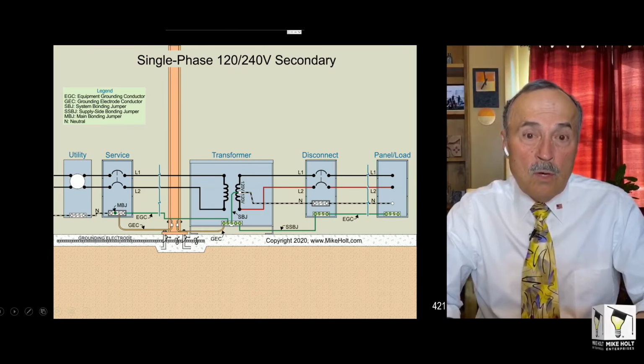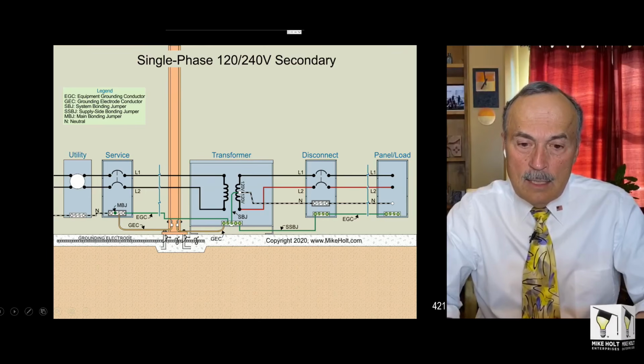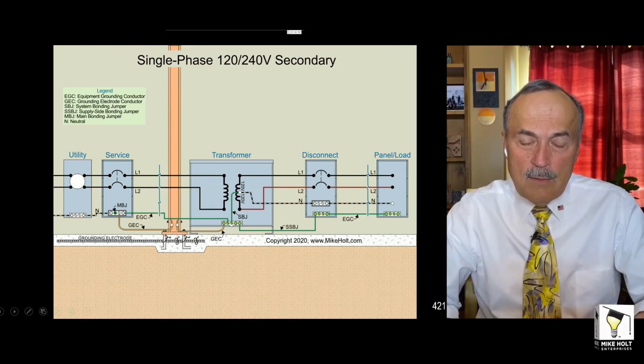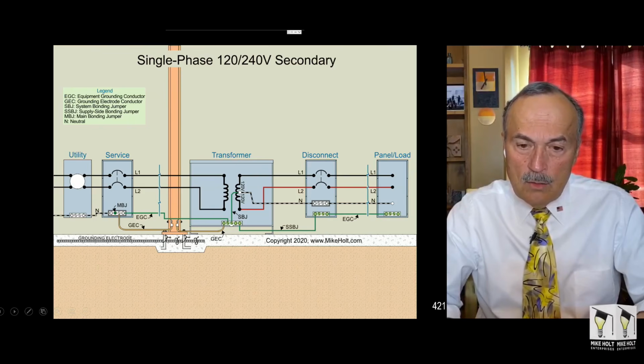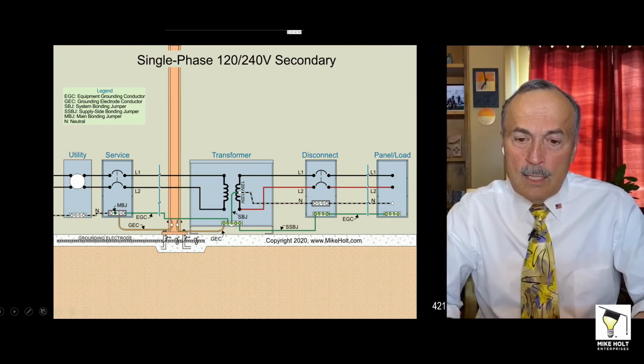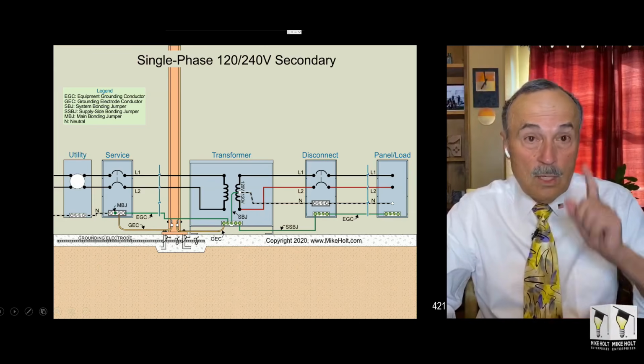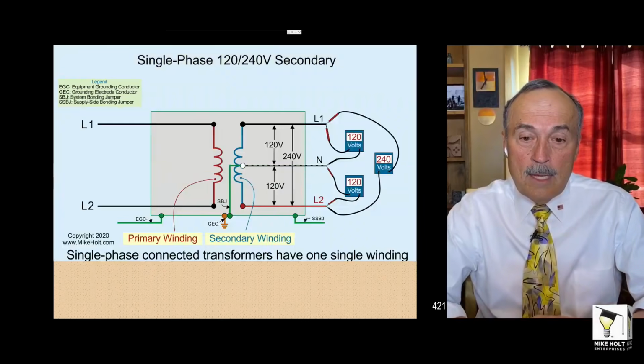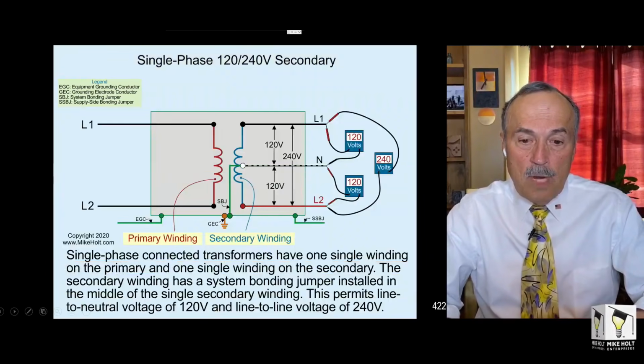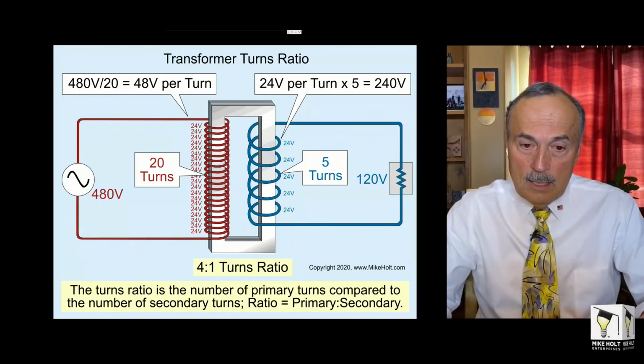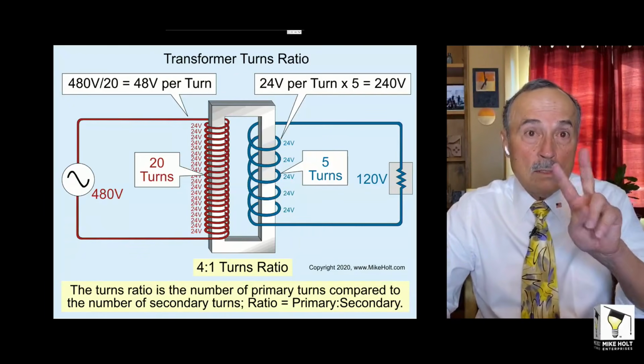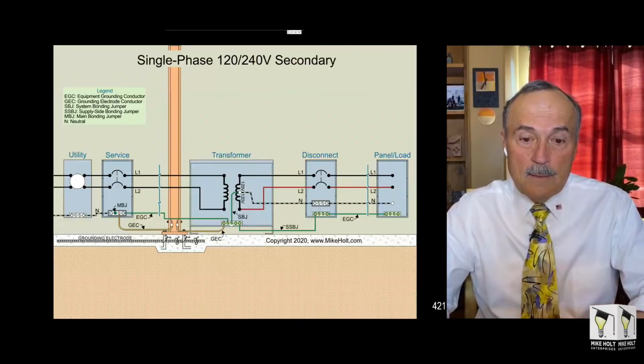We take the midpoint of that one winding, and then we bond that. That means we're going to ground that winding right there, and then we connect it to a grounding electrode, and line 1, line 2, and a neutral. 3-wire. Single phase, one winding. Here's an example of what it would look like. Primary, it looks like this, just one phase.